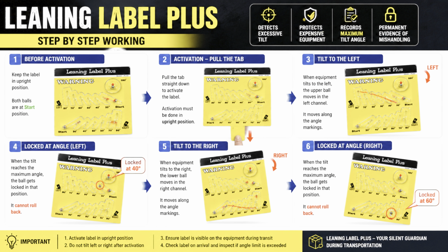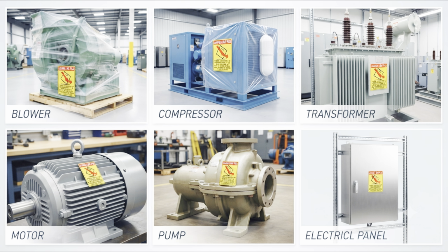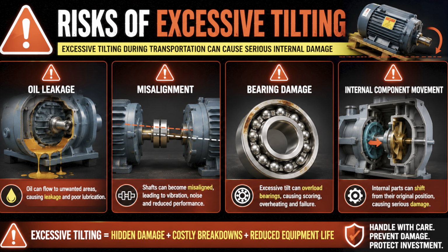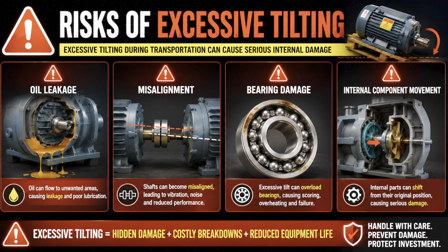for heavy industrial equipment. A Leaning Label Plus is a mechanical tilt indicator attached to expensive equipment before shipment. Its purpose is to record whether the equipment was tilted beyond a safe angle during transportation. You'll commonly find it on centrifugal blowers, compressors, transformers, motors, pumps, electrical panels, pressure vessels. Many of these machines must remain upright during transport. Excessive tilting can cause hidden internal damage even if the outside looks perfectly fine.